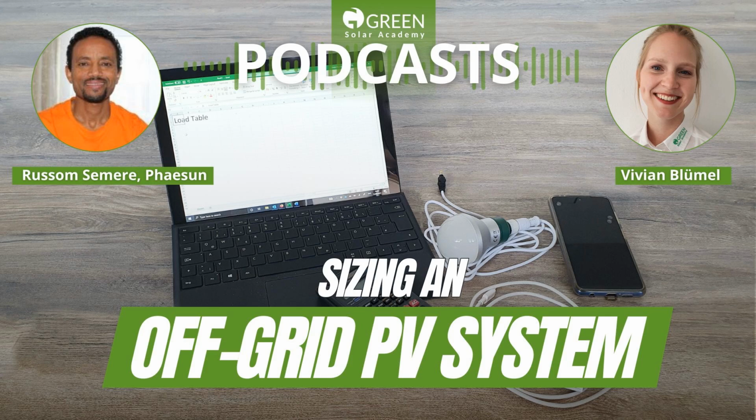And how many autonomy days I use, I have to pre-calculate it. Do I need 2 days, 3 days, 4 days? This depends on the location. Some places have long cloudy days, some places not. So depending on the place, I will decide the autonomy days, and this is important to select the battery size. And also depending on the application. Some applications, like a telecom application, for example, you need to pick big autonomy days, maybe 5 days or 6 days, because these things should work 24/7 and should not be interrupted.